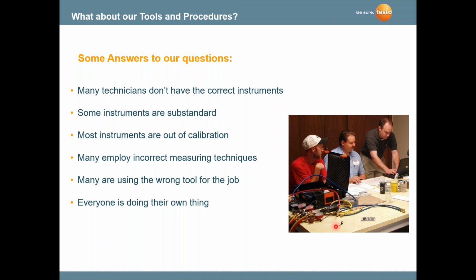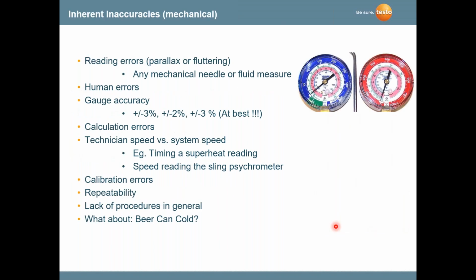And if we look at every question on here, what it comes down to is there's some inconsistency in the way and how we are testing for superheat and subcooling. There are different methods of doing it, different instruments, different gauges. And if we get back to the accuracy of analog gauges, there is less accuracy on analog gauges. You're talking about a gauge that was developed in the late 1800s. It's just a bourdon tube, which as we add pressure, it expands, and as we reduce the pressure it contracts, and that moves a needle on a gauge.